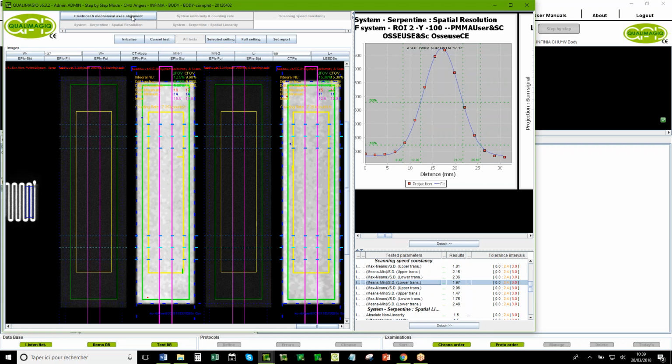And the last, sorry. Yes, do you have a question? Yes, probably a stupid question, but how do you create the uniform image on the whole body acquisition? So how do you position the source? Okay, so it's a uniform source. You install this source on like the bed, and I think they move the couch in this case.